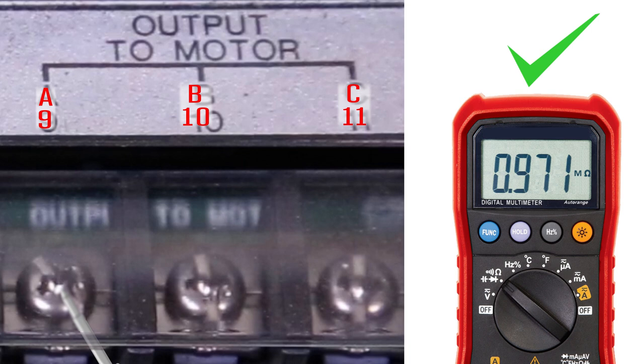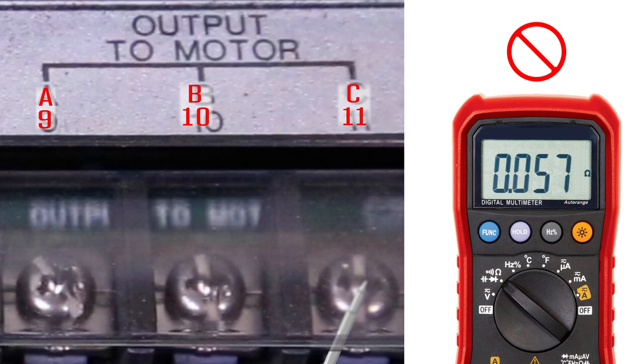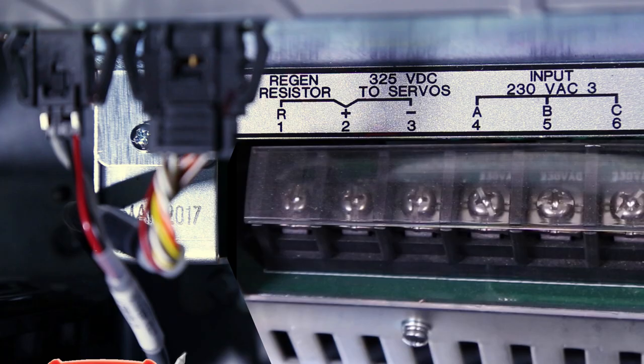The meter should show high resistance readings, typically in the range of kilo or mega ohms. If your meter reads very low resistance, the vector drive is damaged.